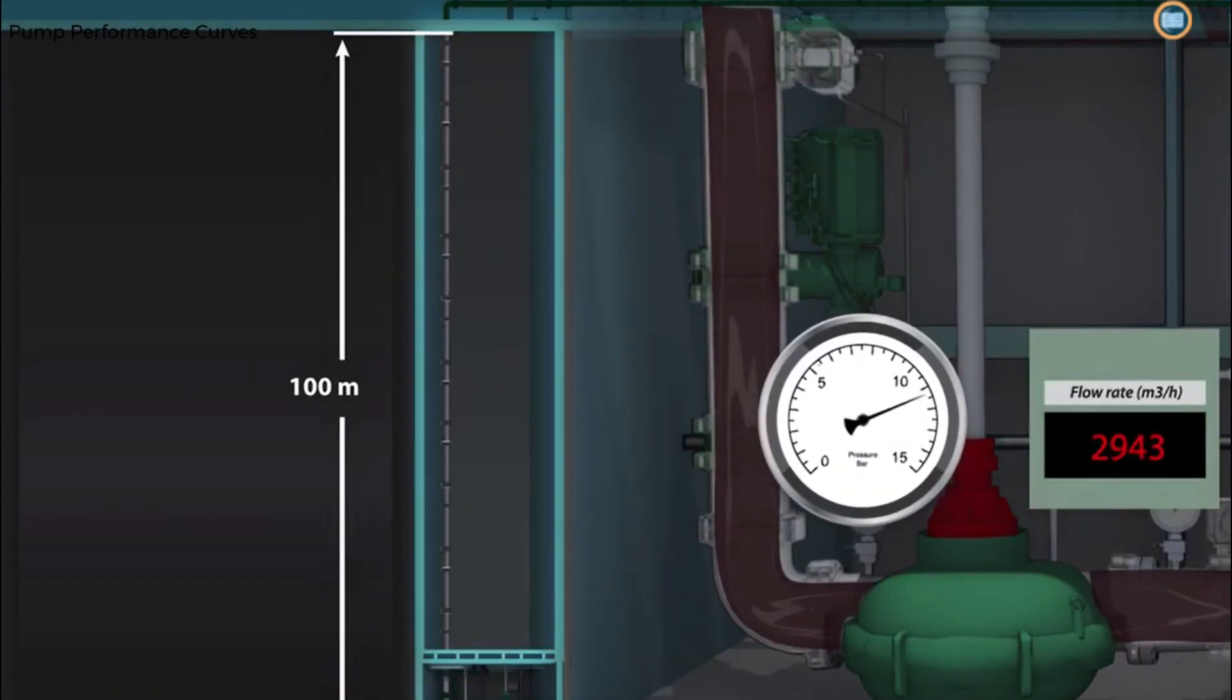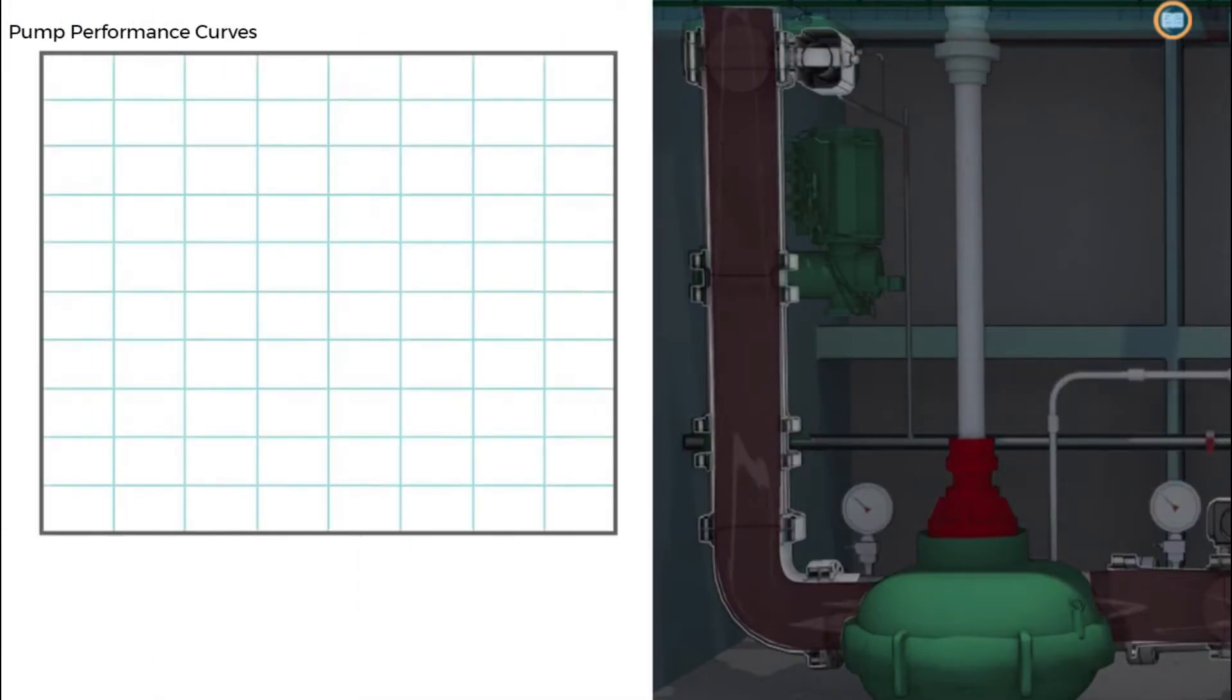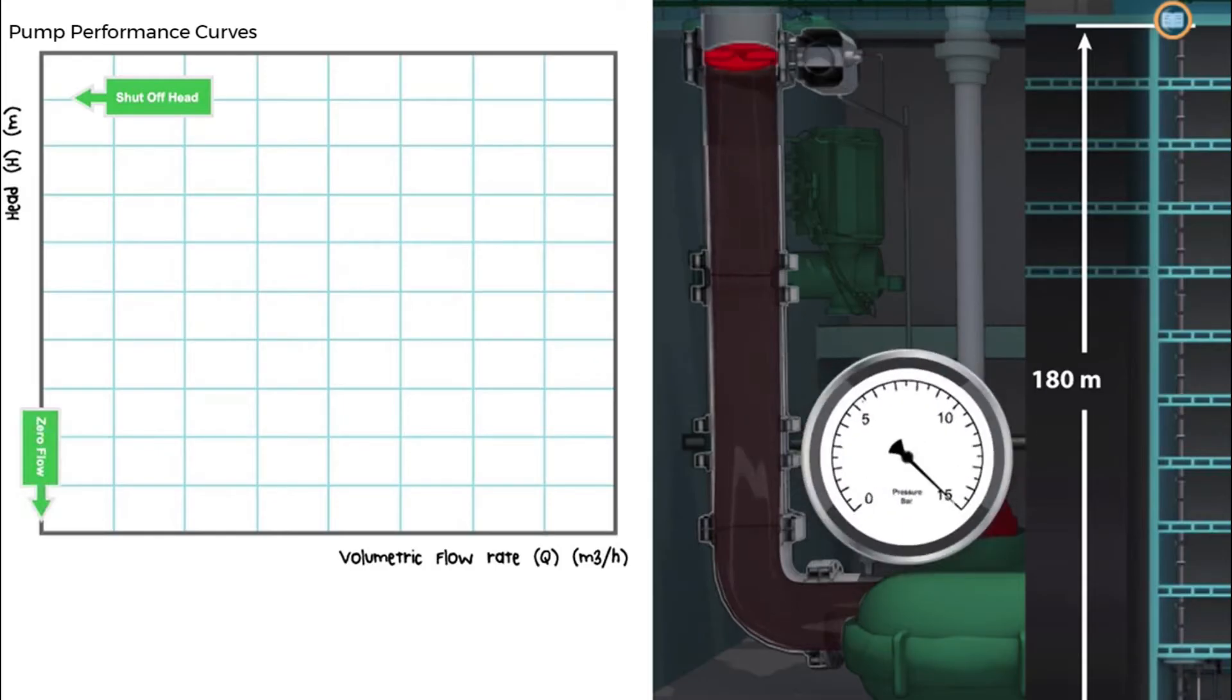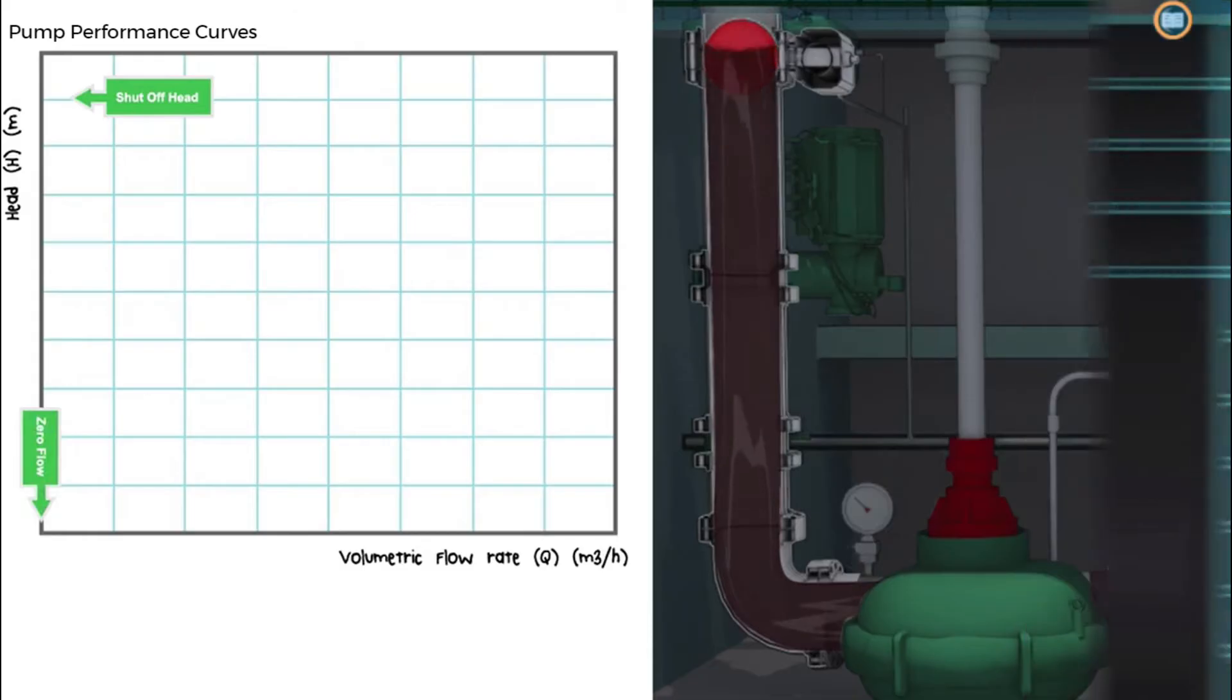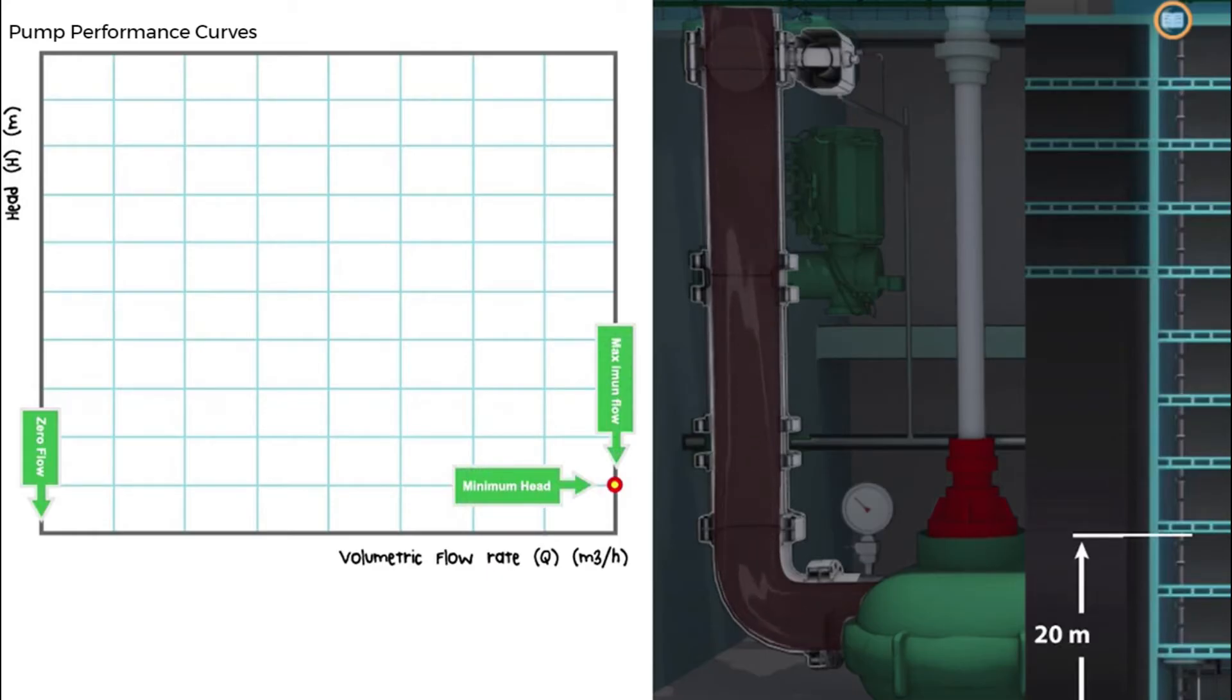How the head changes with flow is a characteristic of a centrifugal pump and this relationship can be shown on a graph here. The x-axis represents the volumetric flow rate in meters cubed per hour. We give this the letter Q. The y-axis represents the head in meters. We give this the letter H. The maximum head that a pump can generate occurs when the flow is zero. We call this the shut-off head and it is equivalent to what would be seen on the pump discharge pressure gauge if the valve was closed against the flow. The maximum flow occurs when head is at a minimum. This would be the case if the pump flow was totally unrestricted.